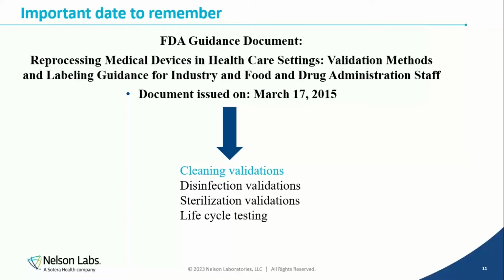And you want to ensure that the date, 2015, that's here, anything beyond 2015 is what you will have to assess at the end, because this is where the changes started to occur for reusable medical devices on test methods. So anything that's 2014 and above, you want to start looking and doing your gap assessments at that point for cleaning validations.